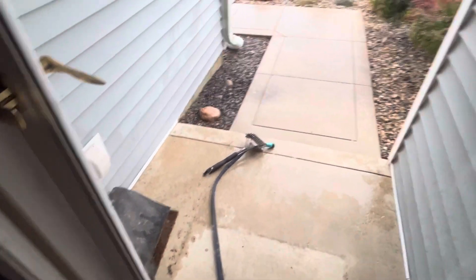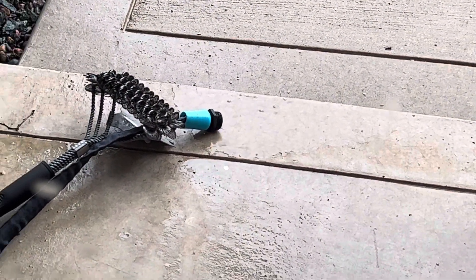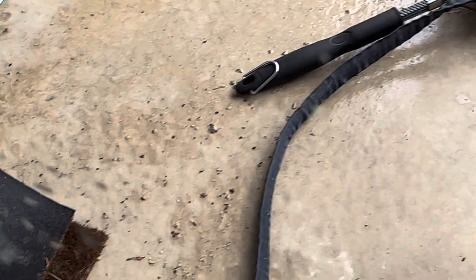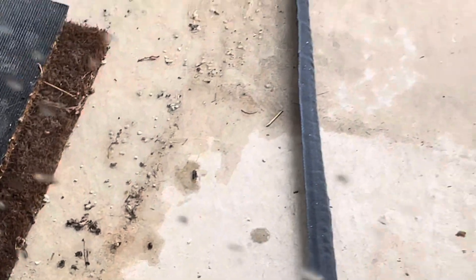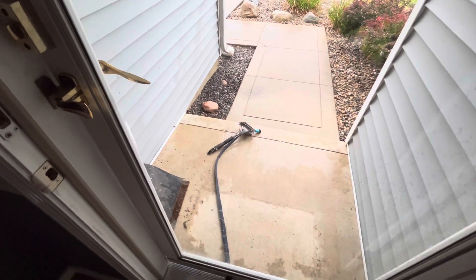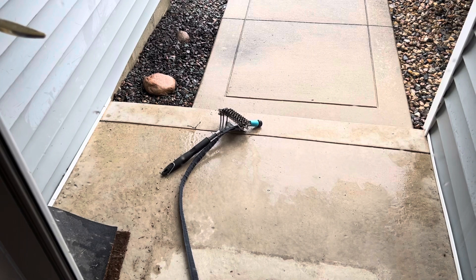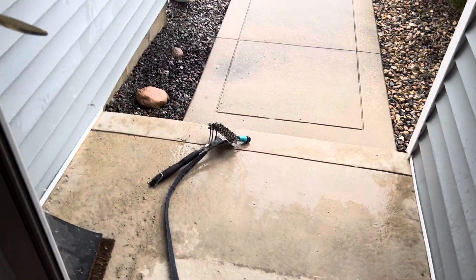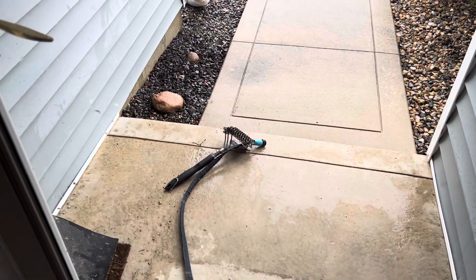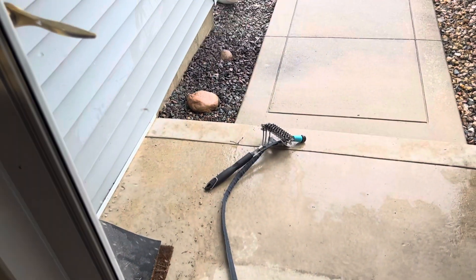I had the water turn on earlier and that was when it was really whipping around. Let's zoom in — you can kind of see a little bit of sediment there. Some of this is just dirt, but all these little specks are like the sediment buildup. They installed that Ion Polarization device maybe a couple months after I did the last flush, so some of that stuff might be from prior to them installing it. Probably the rest is just the fact that these things aren't perfect.